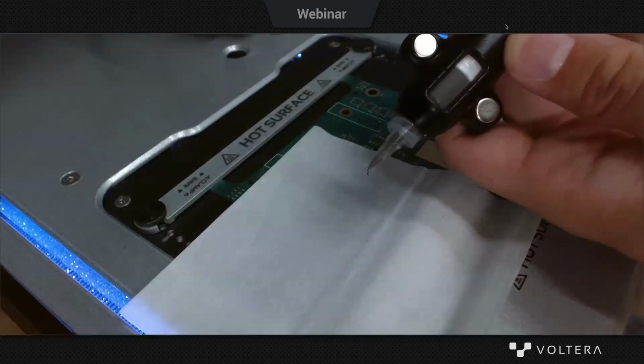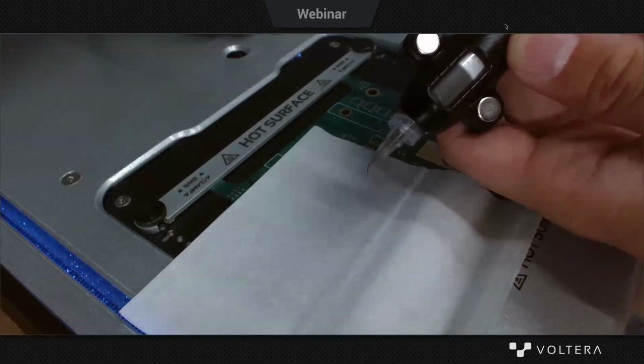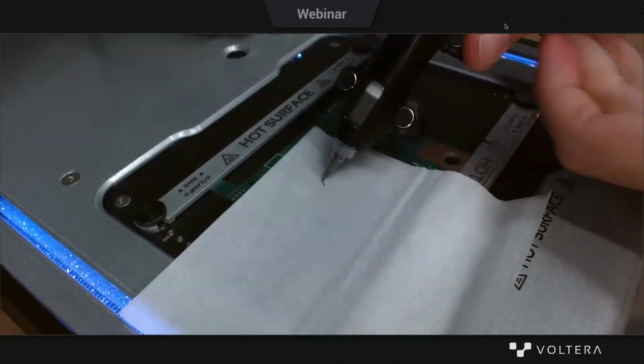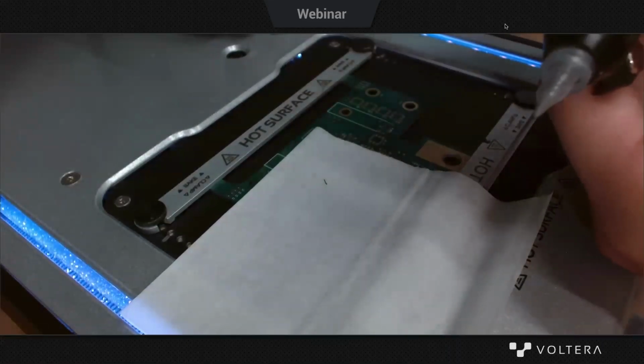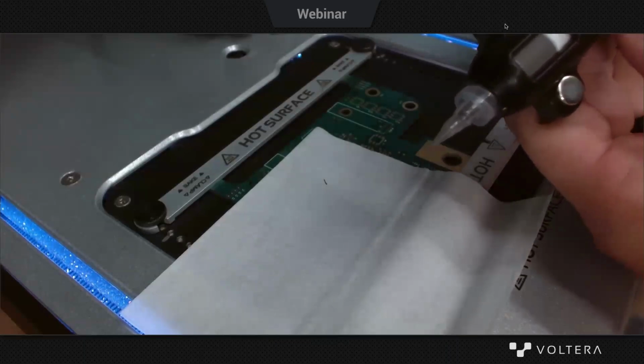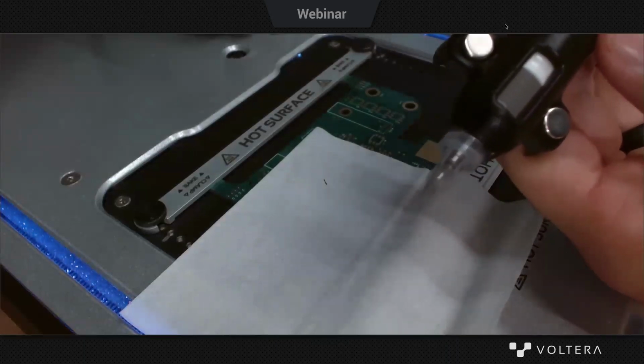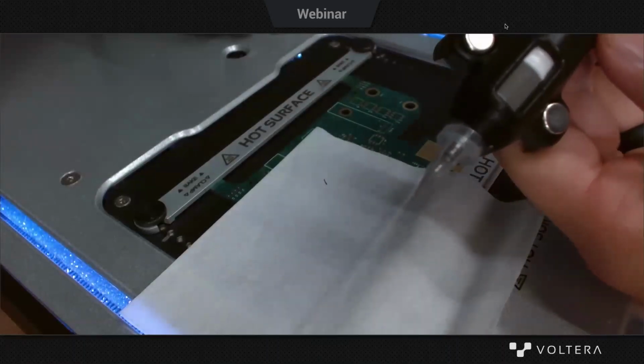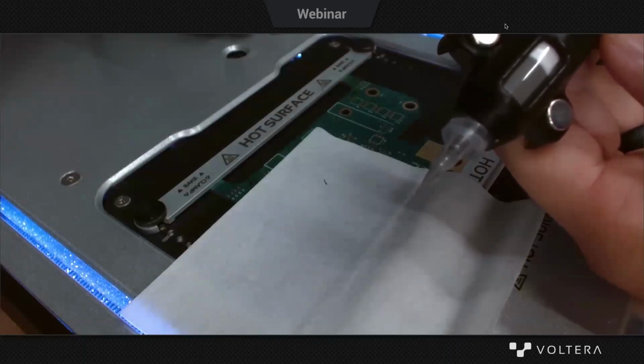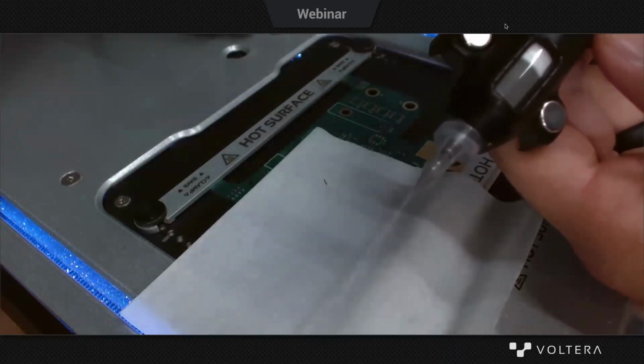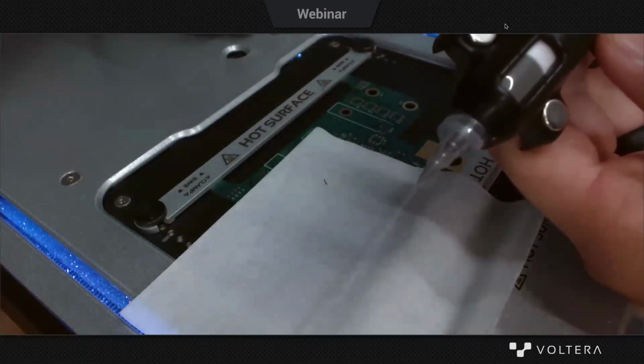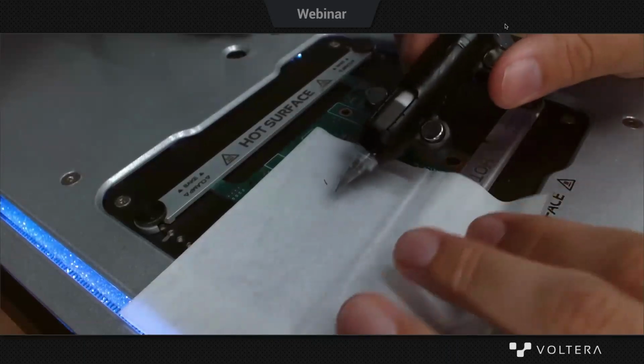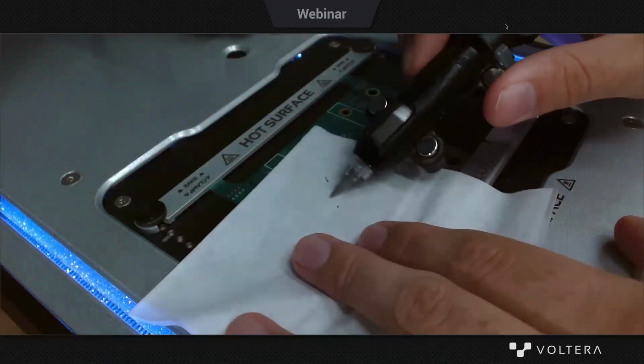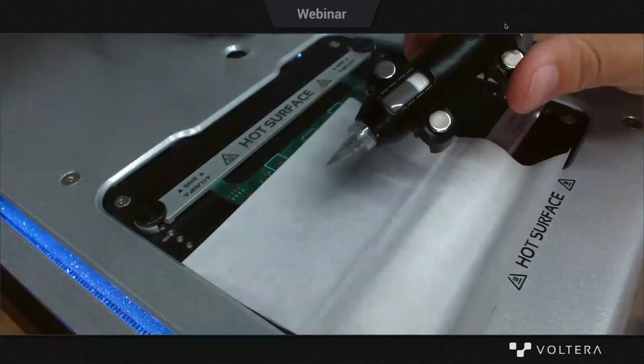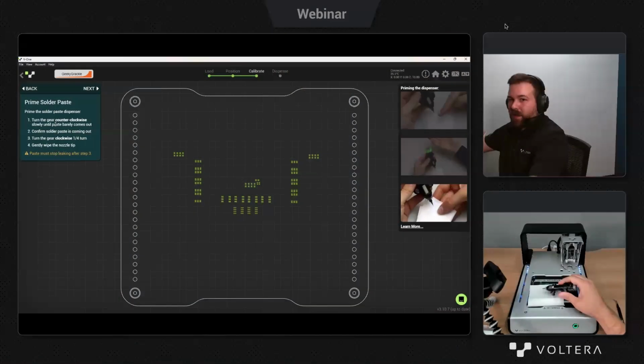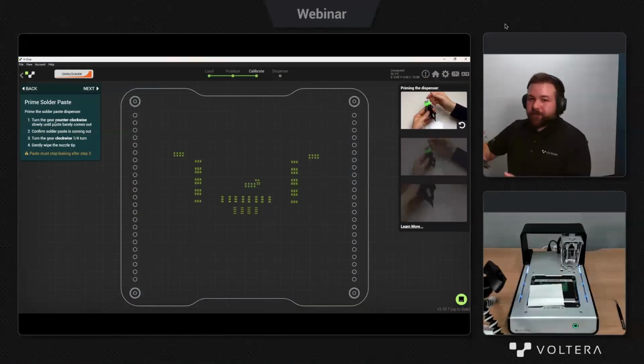And then I back it off about a quarter or a half turn just to make sure that the flow is stopping. So what I'm doing here is basically getting the cartridge to the point where it's on the edge of flowing, so that it could be ready to be dispensed. And so I'm just setting the position of the actuator for that. Now, it's not incredibly important that I get this spot on. We'll be able to dial this in the software here as well. But yeah, that's getting the cartridge primed.